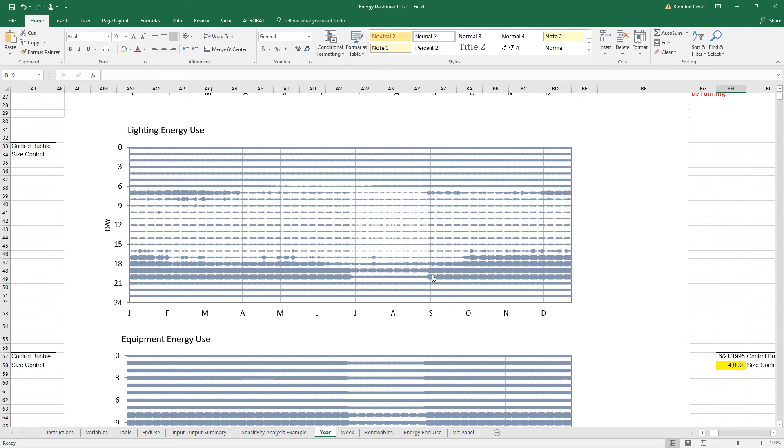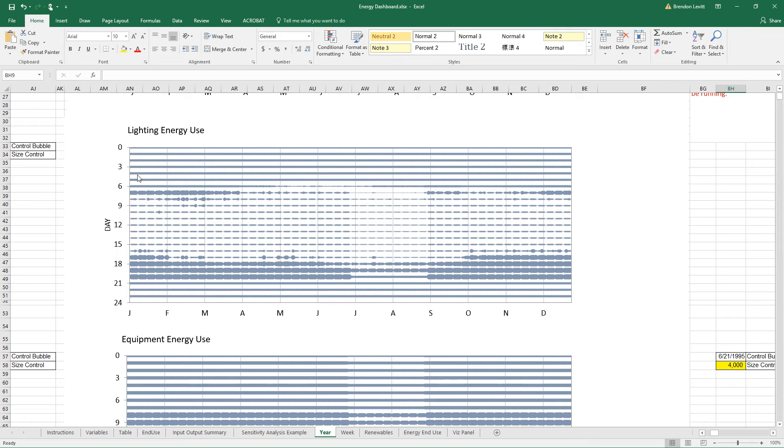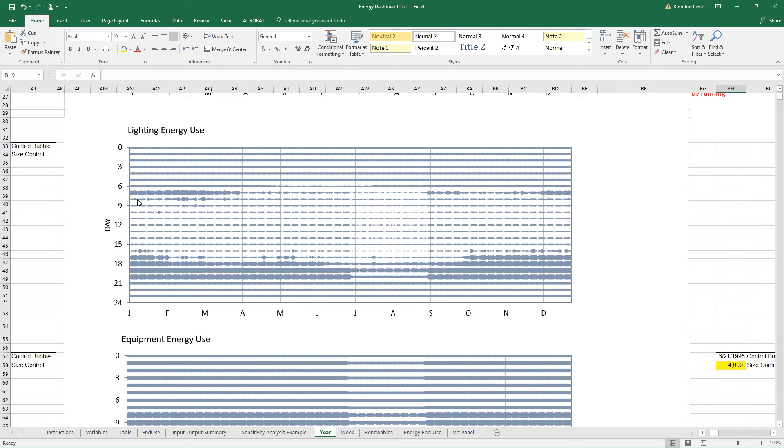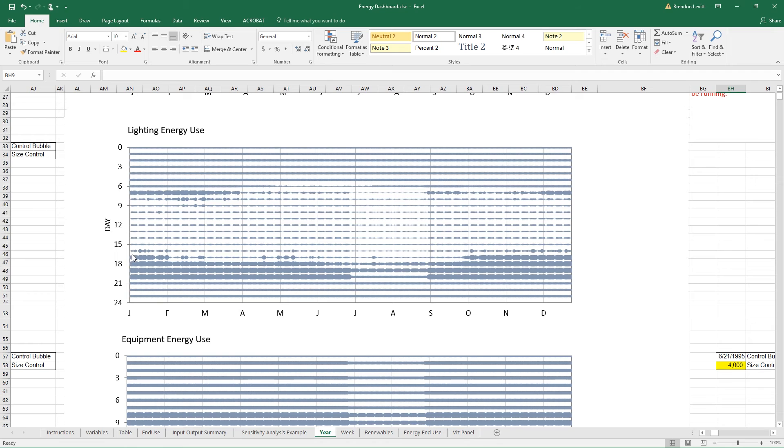This, of course, depends on your actual schedule. So in this schedule that I've got set up, it looks like there's some lights on overnight. And then at 7 a.m., someone comes on and turns on all the lights. And then by 8 a.m. the sun is up and we're getting some pretty good illuminance. Then by about 4 p.m., we're not getting enough illuminance.